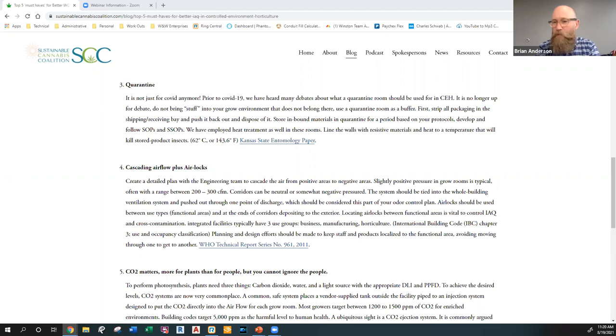the pallet, anything that might contain somebody else's problem that you don't want to make your problem. Now move whatever consumable you're bringing in from the outside into a quarantine room. We reference this Kansas State entomology paper, and on the blog you can get a link that shows what temperature will kill soft-bodied pests. It's 62 degrees Celsius, about 143.6 Fahrenheit. So we use the same insulated metal panels in a quarantine room, put a sauna heater in there, and heat the room up to about 150 degrees for an hour. We're killing everything that could possibly negatively impact your plants.